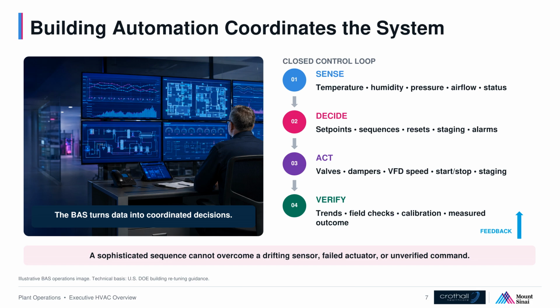Here's how a small failure travels. A sensor drifts. The controller makes the wrong decision. A valve, damper, drive, or piece of equipment takes physical action. The room's temperature, humidity, airflow, or pressure drifts. Then patient care, research, comfort, staffing, energy, or room availability is affected. Operations sees alarms, troubleshooting labor, call-ins, or emergency response. Financially, the same problem may create simultaneous heating and cooling, excessive fan or pump speed, and avoidable cost. Major equipment can look healthy while the system performs incorrectly. Trends, calibration, field checks, and leading indicators catch that gap before the room becomes the alarm.